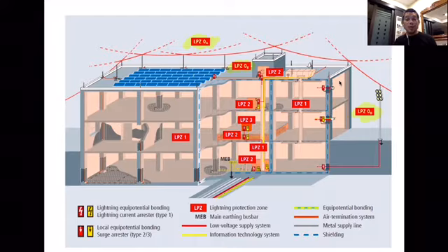But also LPZ1, if you have shielding from magnetic radiation, is also defined as such when you reduce the magnetic radiation by some sort of shielding. As you can see there, the blue dotted line here is actually a shielding to reduce to zone 1. But for the conduction, you have wires that go in. You can use SPDs to go to Z1, Z2, even Z3.